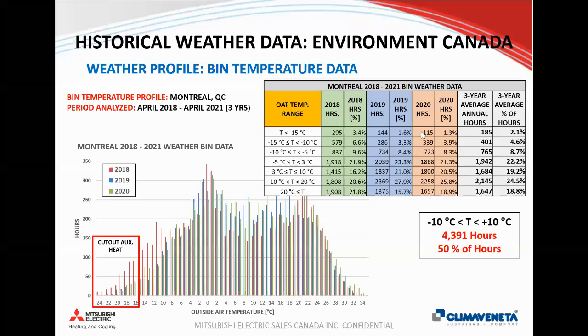So as you start to look at some colder climates, you see that you do spend more time at colder temperatures, seeing more and more hours, but there's still a significant majority of the hours where you can still provide useful heat from a heat pump as low as -10 typically, and we'll talk about why I picked that number to show you today in a couple slides. But we have the mentality that we need to have a heat source that's going to work at all times under all sets of operating conditions. And now we're also saying that we want it to be low carbon. So we want to have our cake and eat it too a little bit.